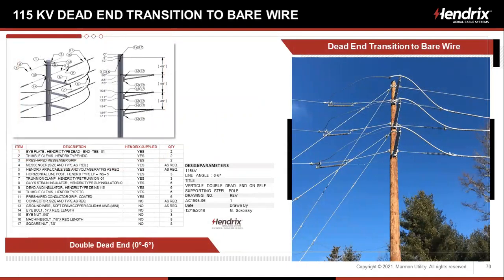There's a 115 kV dead end transition to bare wire. So again, you can see here we're coming out of the dead end grip around a standoff insulator, and then making that connection directly onto the bare wire. And of course, we have our lightning arrestor there to prevent any lightning surges hitting that bare wire and getting into our covered conductor.